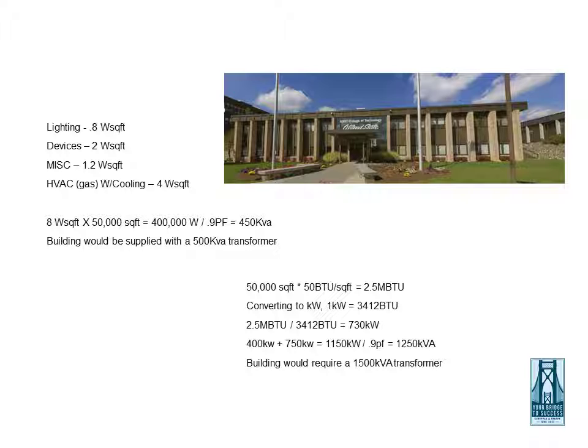Now, taking a potential gas load of 50 BTUs per square foot and our 50,000 square foot building, the possible gas load would be 2.5 million BTUs. With a conversion of 3,412 BTU per 1 kW, a potential additional load of 730 kW would be added to the existing load of 400 kW for a total of 1,130 kW.